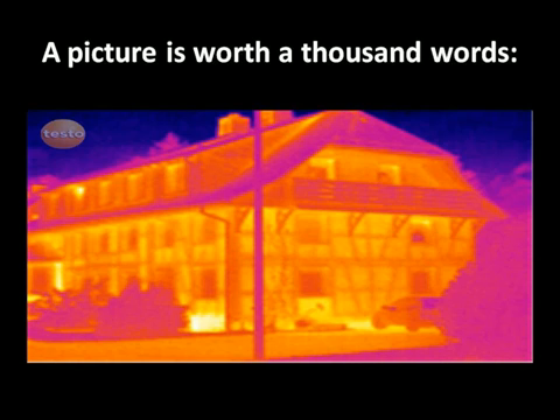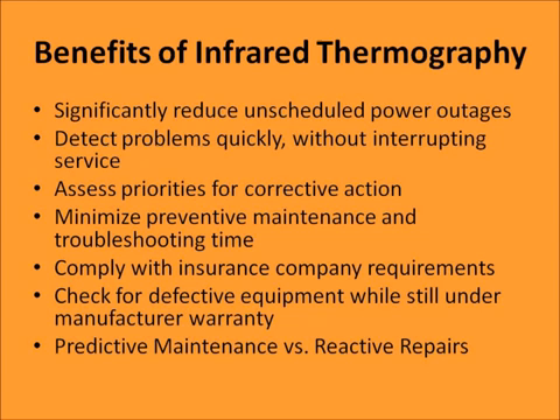We're all familiar with the saying, a picture is worth 1,000 words. Here are some benefits of infrared thermography. It helps significantly reduce unscheduled power outages, detect problems quickly without interrupting service, assesses priorities for corrective action, minimizes preventive maintenance and troubleshooting time. It helps the client comply with insurance company requirements, check for defective equipment while it's still under manufacturer's warranty, and most importantly, it allows for predictive maintenance versus reactive repairs.